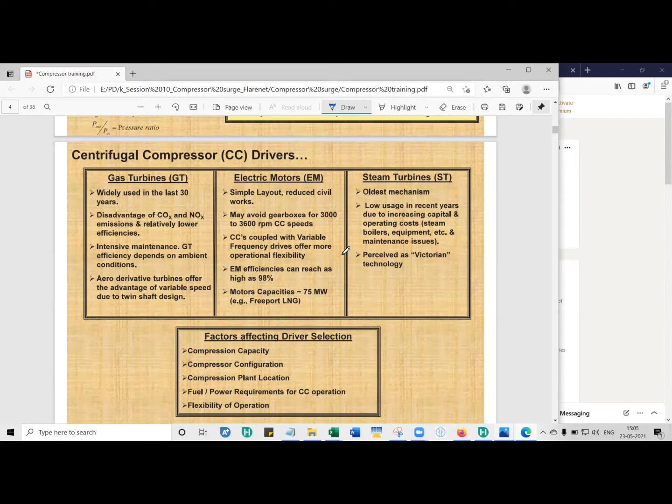When you're at mean sea level, the air is more dense. When the density is more, the turbine does not have to struggle to deliver more output. But let's say you're in a hot country, the air temperature goes up, because the gas temperature is hot, naturally the power output decreases.